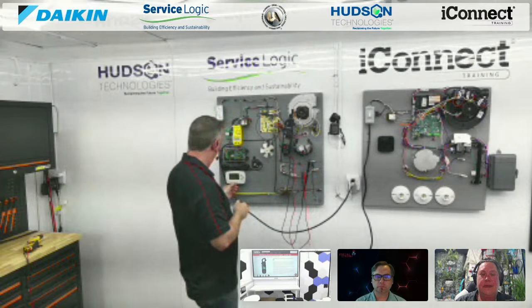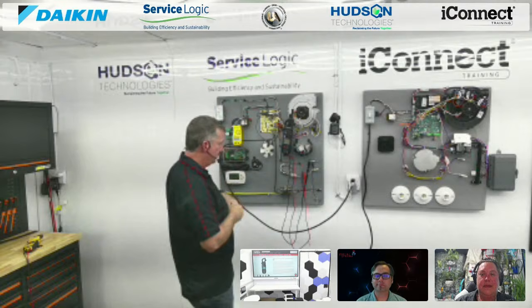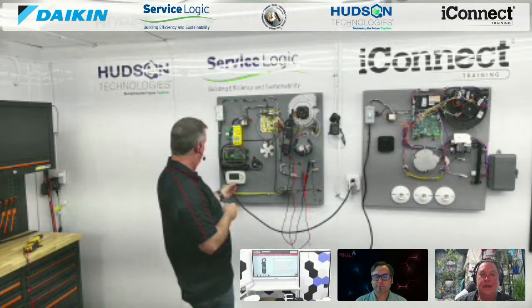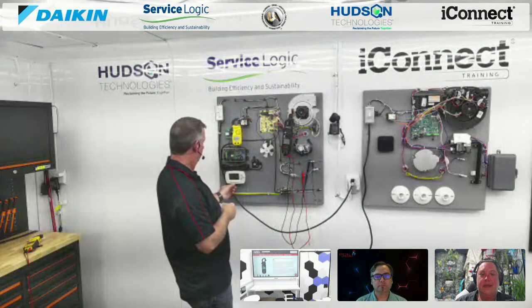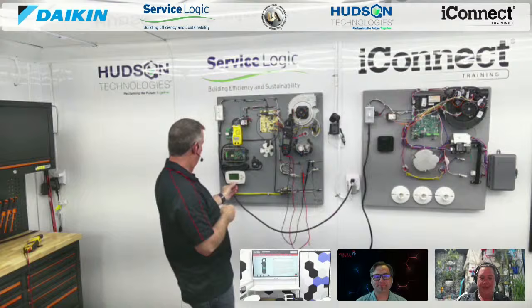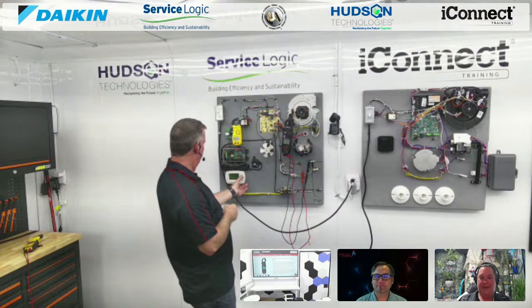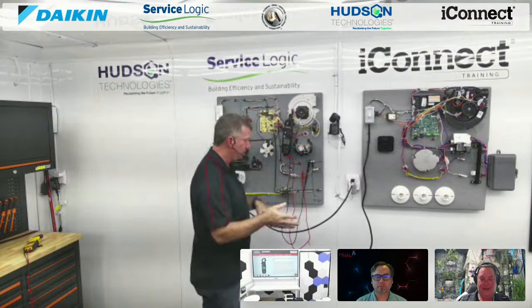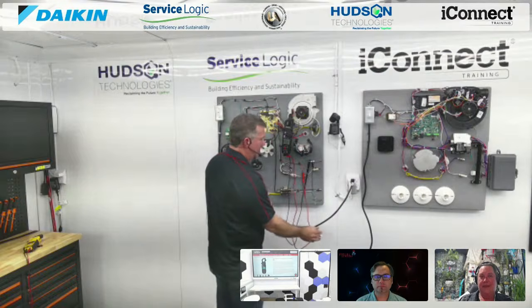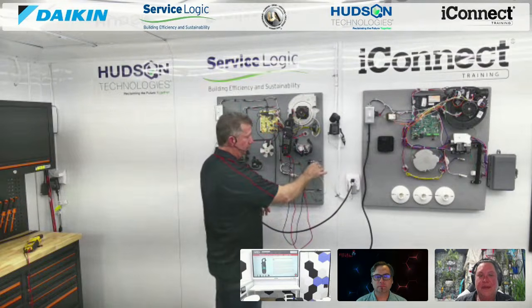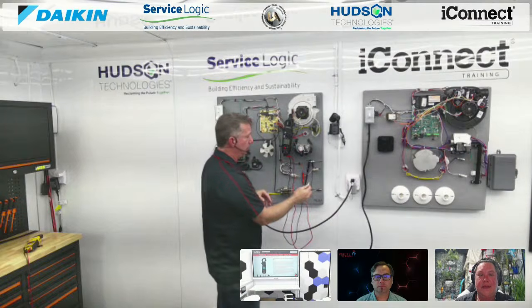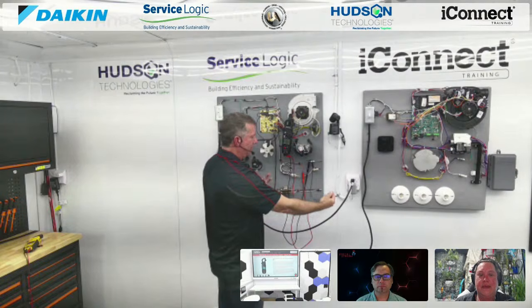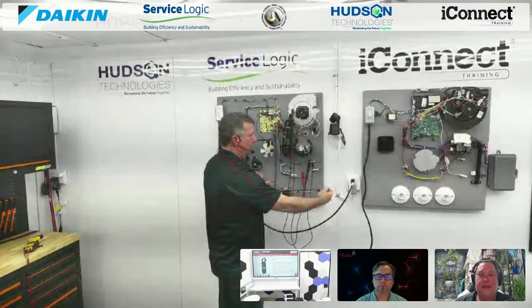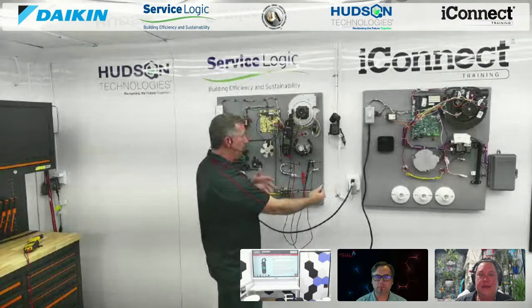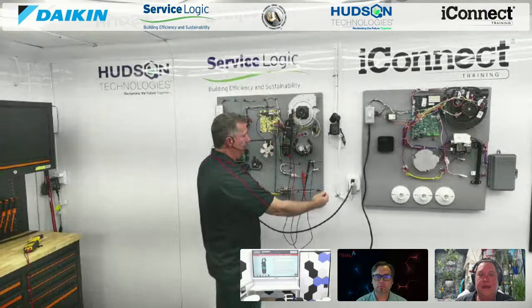So we're just simply going to do that. We're going to fire this thing back up. We're going to put it in heat. As soon as our thermostat resets, we'll crank our temperature up a little bit. And off we go. But we have to follow our sequence. So it's great to be able to show the student that sequence of operation. If we connect early on, we're actually going to go into a fault. But if we keep our timing properly, we'll be able to create our electrical load, and the circuit board won't know any different. But we have to have a meter that is reading microamps properly.